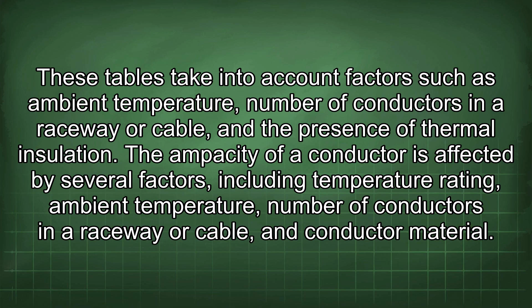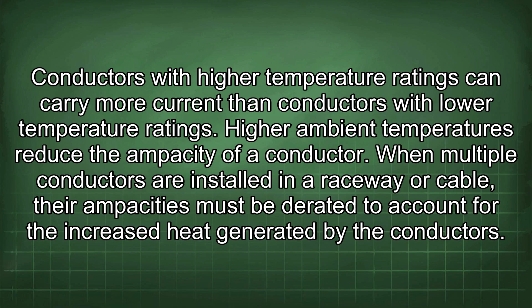Conductors with higher temperature ratings can carry more current than conductors with lower temperature ratings. Higher ambient temperatures reduce the ampacity of a conductor. When multiple conductors are installed in a raceway or cable, their ampacities must be derated to account for the increased heat generated by the conductors. Copper conductors have a higher ampacity than aluminum conductors of the same size.